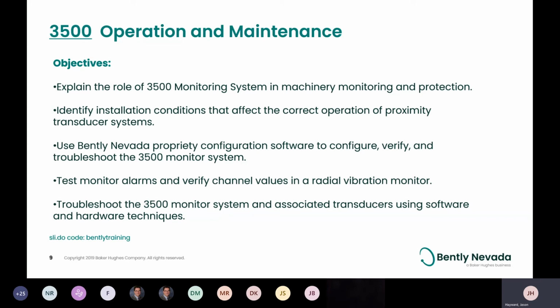Along with that, we look at how to use this Bently Nevada configuration software: how to configure 3500 racks, how to verify your readings, how to test monitor alarms, how to verify channels, and troubleshooting the monitoring system, software, hardware, and transducers.